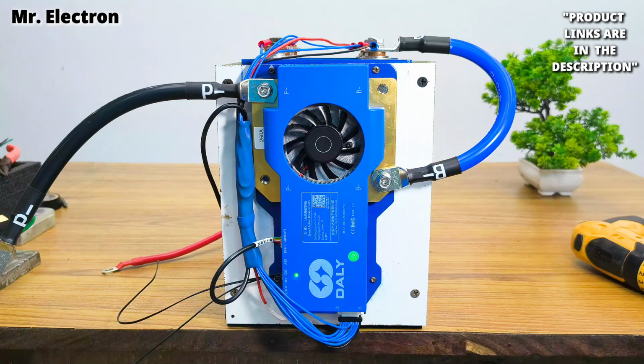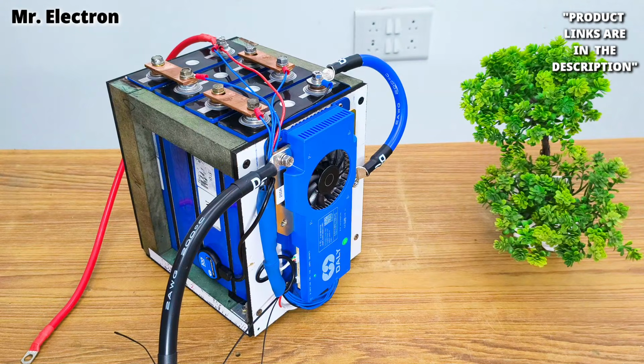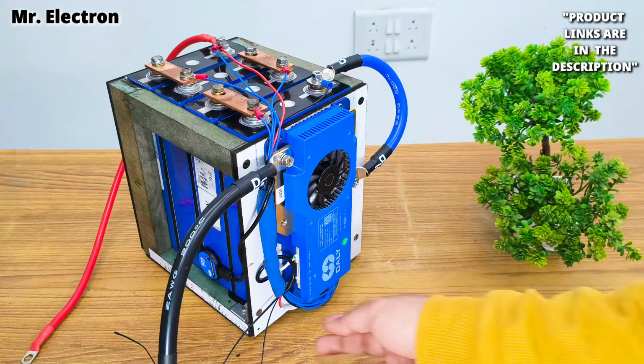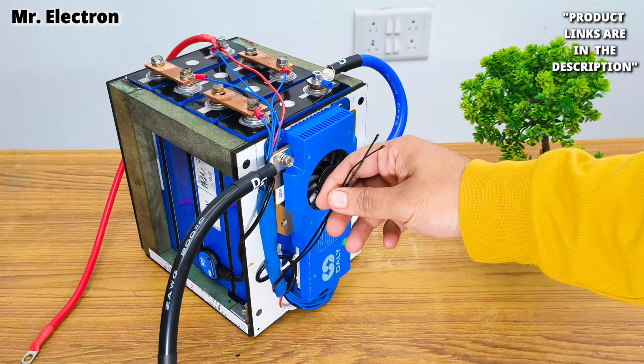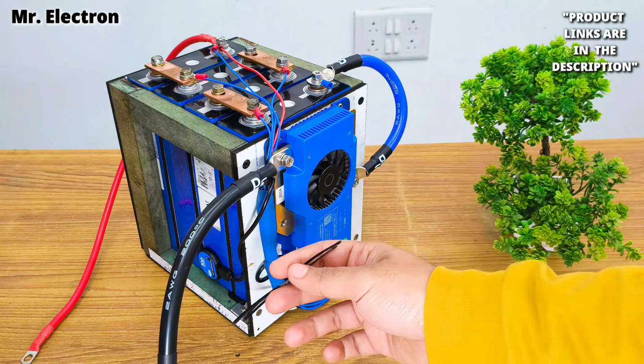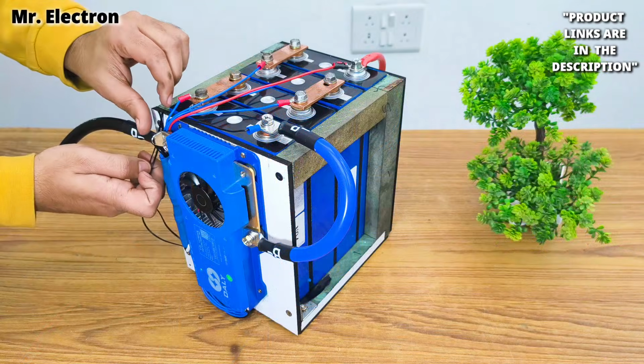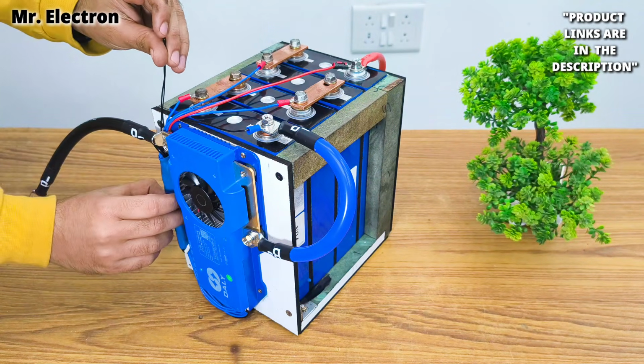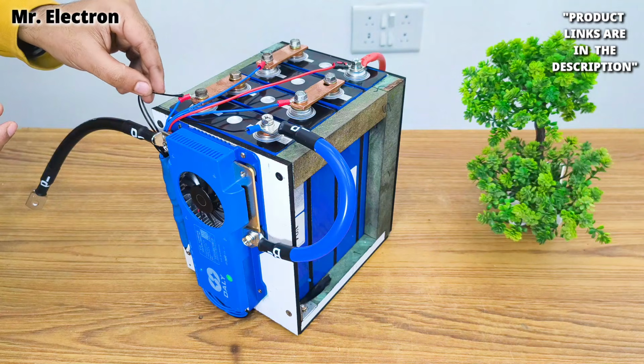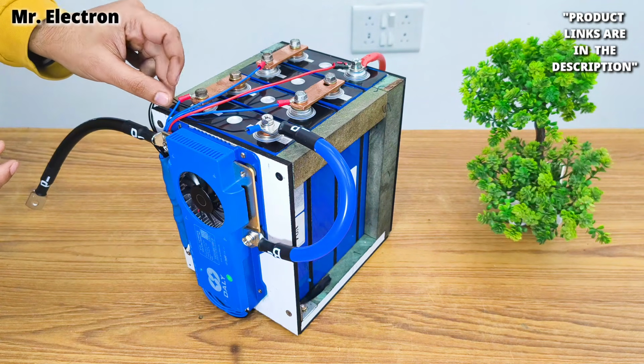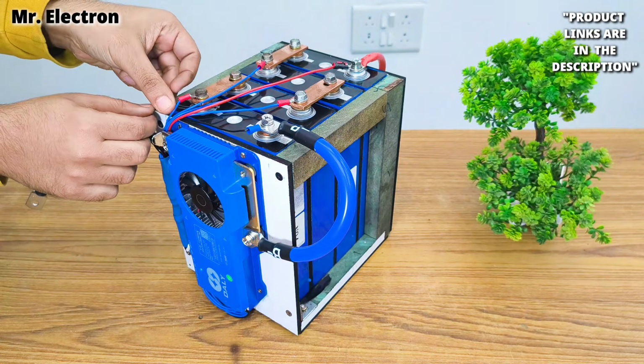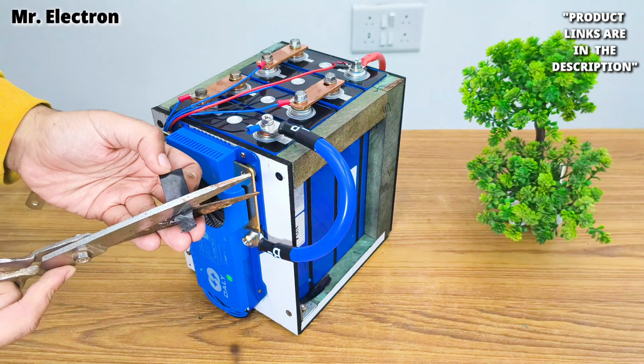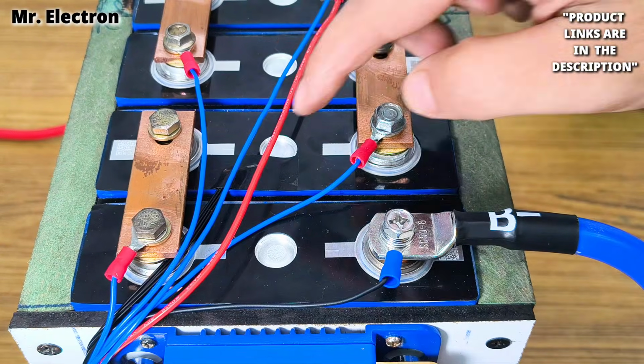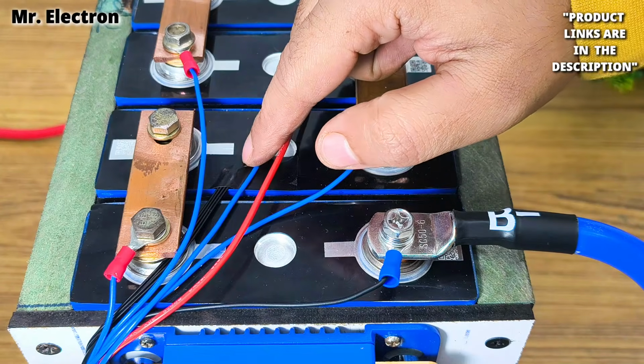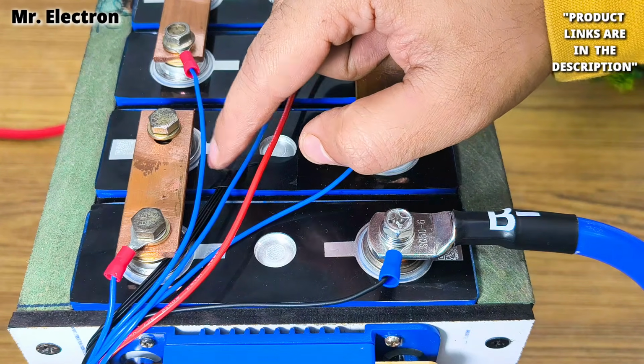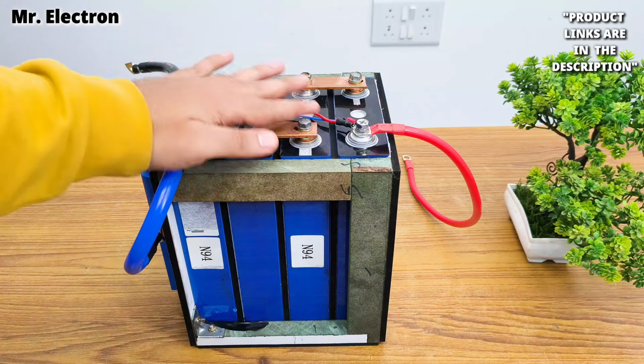Next comes another very important part, connecting the final temperature sensors to the battery. These are going to sense the temperature and tell the BMS if everything is fine or not. You have to take these sensor wires out, and from below the cable wires take these sensor pointers to the second battery, then use this black tape. These sensor wires will be placed on the battery surface in the middle of the two terminals of the battery. Finally, the connection parts are fully complete.